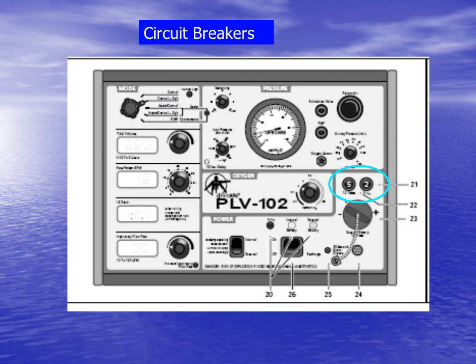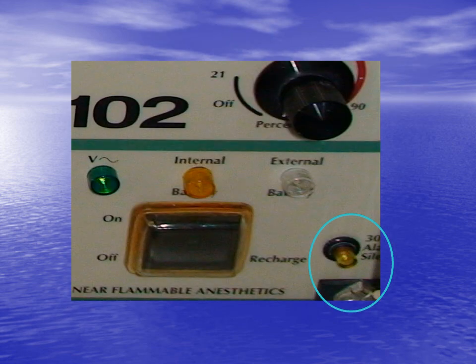Internal circuit breakers on this ventilator can be tripped, temporarily disabling its function. Push the button on the front panel to reset the breakers, but if the vent repeatedly trips the breakers, do not use the ventilator. The alarm silence is 30 seconds in duration with an automatic reset. The yellow LED shown here lights when the alarm silence has been initiated.